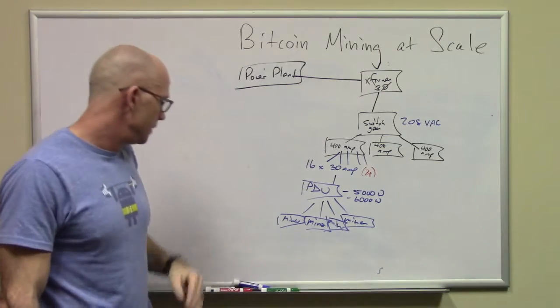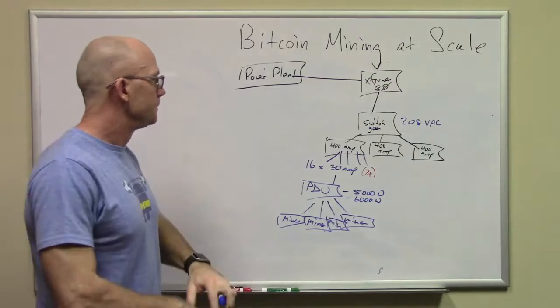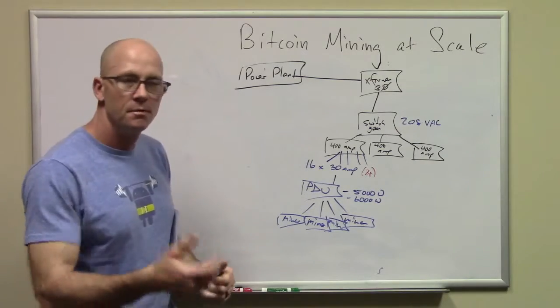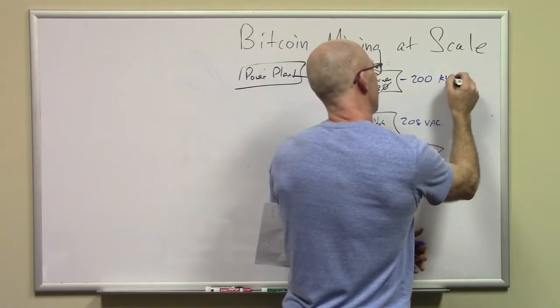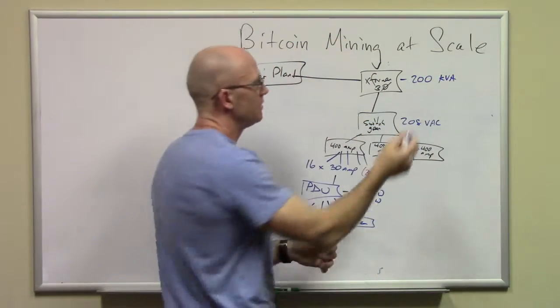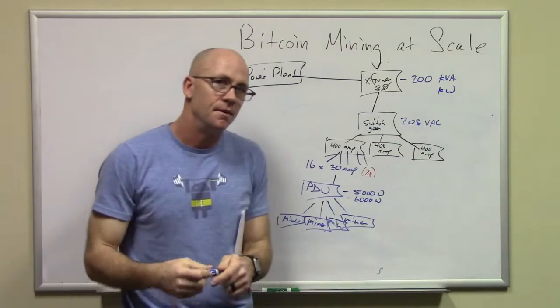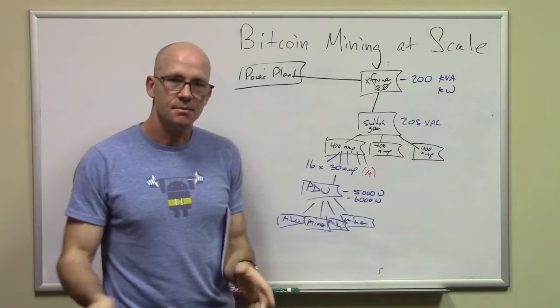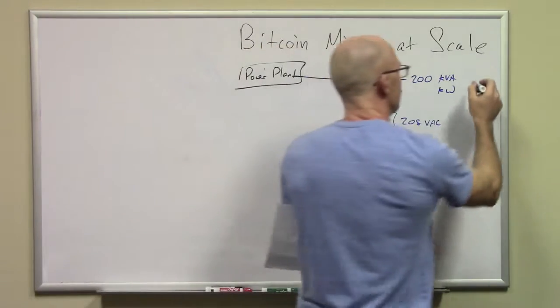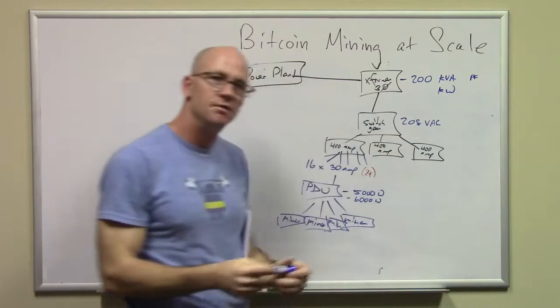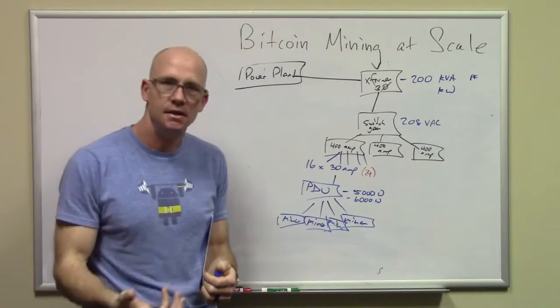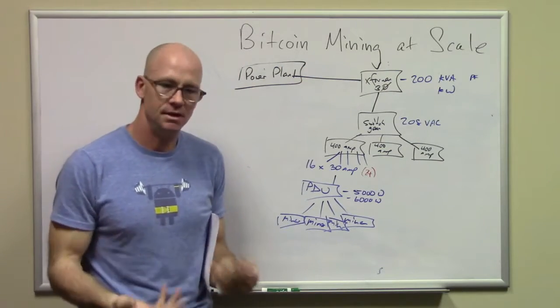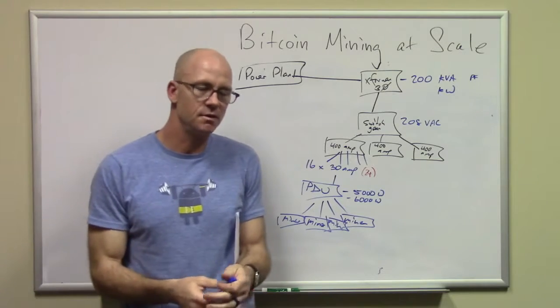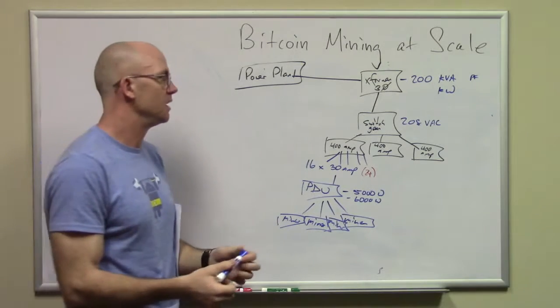This example is for about 200 miners, which I was using in the previous example. This would probably have to be around a 200 kVA transformer. kVA is kind of like kilowatts, it's just a little different - VA is volt times amps. So kVA takes into account the power factor. Rotating machinery tends to have a power factor where the impedance makes electric use inefficient, which is why transformers tend to be measured in kVAs.